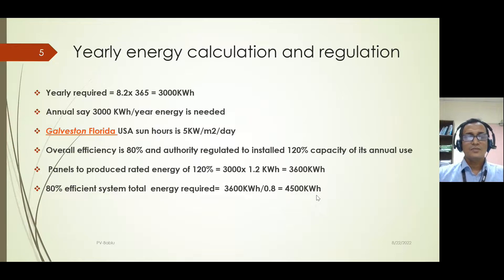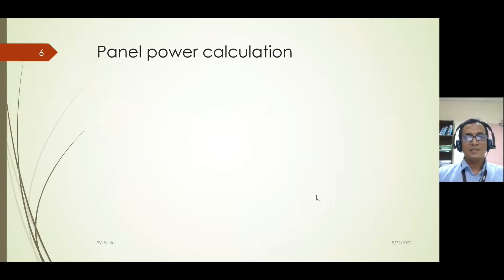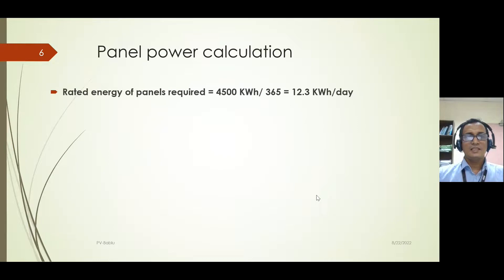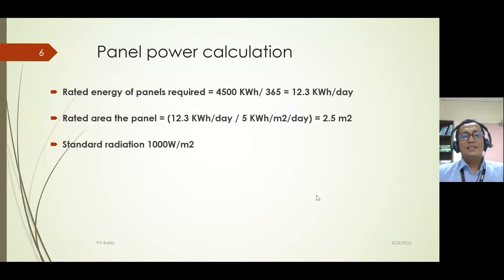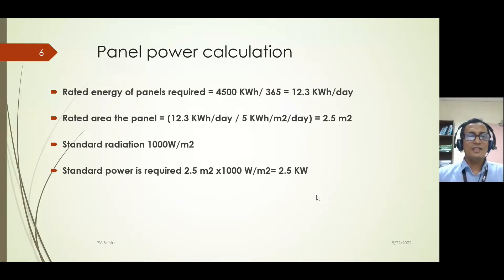At 80% efficiency, we need to install about 3600 kWh divided by 80%, giving a total required capacity of around 4500 kWh. For the panel power calculation, the rated energy required is 4500 kWh for 365 days, meaning each day we require around 12.3 kWh. With insolation of 5 kWh per meter square per day, the effective panel area required is around 2.5 meter square for generating 12.3 kWh per day. At standard irradiance of 1000 W per meter square, 2.5 meter square requires about 2.5 kW.